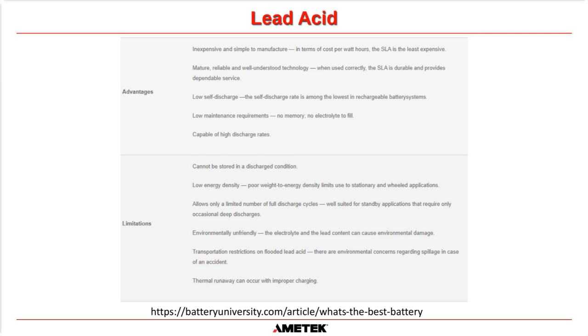They allow only a limited number of full cycles, so they are well suited for standby applications like UPSs. They are also environmentally unfriendly. The electrolyte obviously contains sulfuric acid, and the lead needs to be recycled. So they're not fantastic for the environment. And there are transportation restrictions on flooded lead acid cells, basically due to spillage. If you have a wet cell battery with electrolyte in it, then it is considered hazardous waste. And thermal runaway can occur with improper charging.